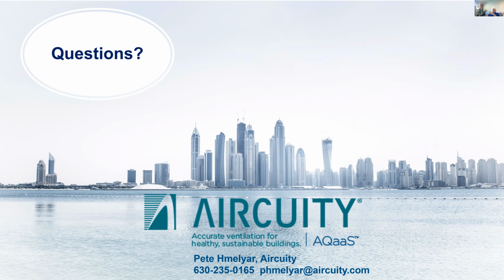In there, particles are a big thing, and we're looking at using the TVOC sensor to look for ammonia. Even the CCAC recommends that even if you're not lowering the air change rate, you ought to be monitoring the quality of the air for TVOCs and particles and actually CO2 and humidity levels. So that's now a growing opportunity for us in Canada, and we've done a number of jobs now. The University of Lethbridge was a really big new construction we did. Whereas before you had to run a fixed air change rate, I think between 15 and 20 in the vivarium, now the guidelines allow you to lower it. So vivariums are a big area.